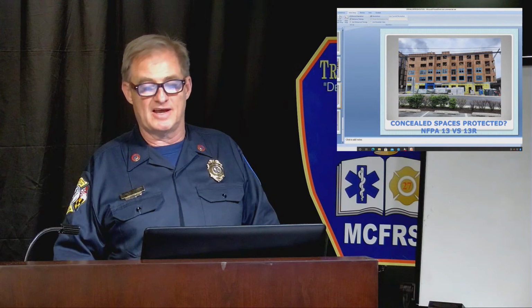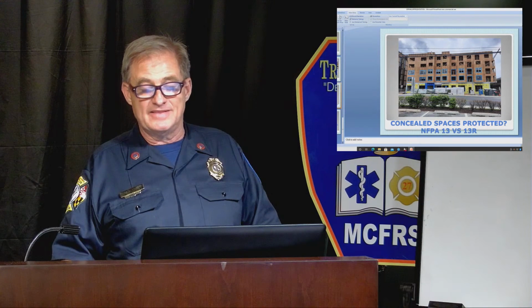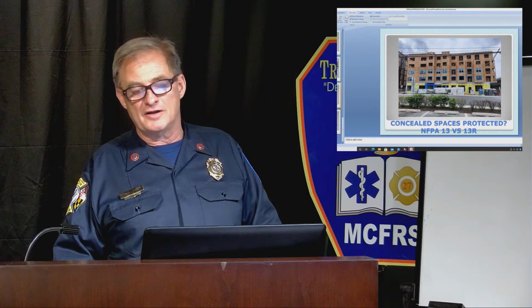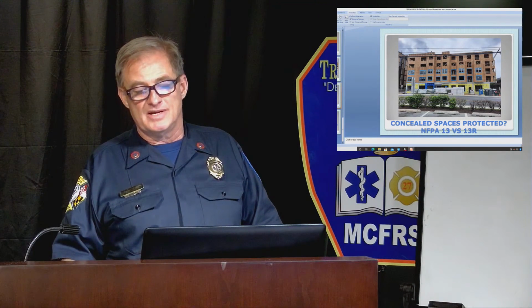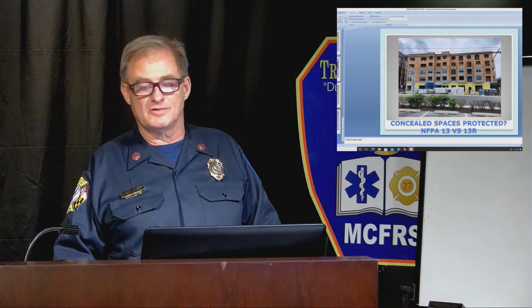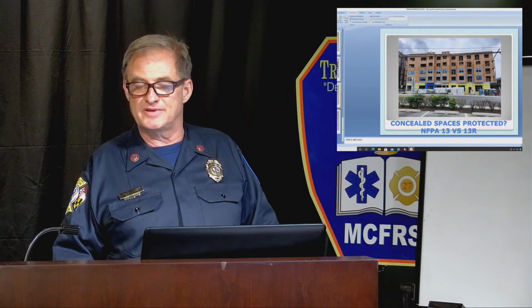It was a fully occupied building, and in the end, it got a lot of news attention. But in the end, there wasn't a single civilian death or injury. So you'd have to say that the sprinklers did exactly what they were designed to do. Protect life. Property protection is important, but in this case, it's going to be a secondary benefit of a 13R system. So I hope I identified the difference between those two systems.